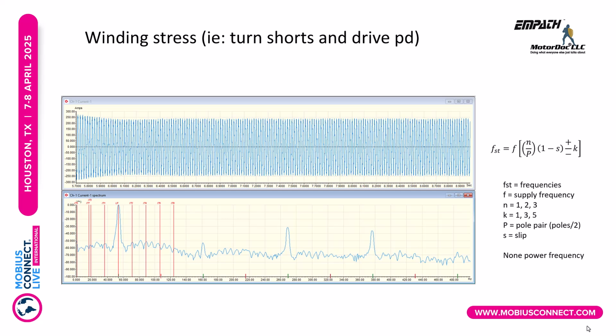Winding stress, which also existed in this one, is a special calculation. It does, as it turns out, and we published a paper on this in 2021 for IEEE, that it's not really a winding short, which was the original purpose of the calculation. It actually turns out to be things like improperly set VFDs, partial discharge going on inside the machine, and other conditions that are occurring that cause sparks and discharges in the winding, little lightning storms that'll be picked up in the field.